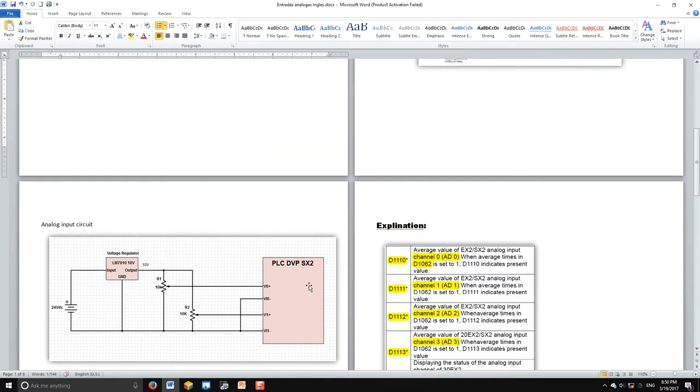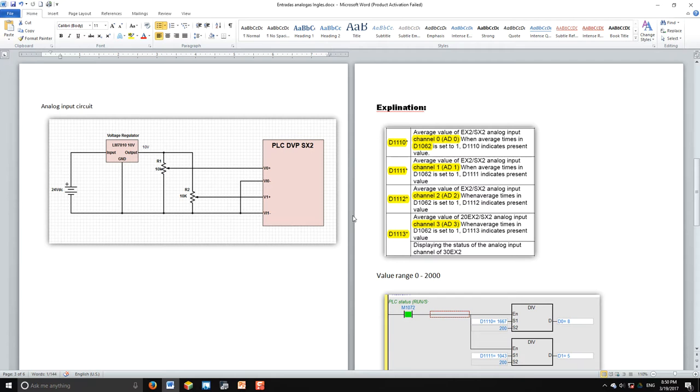Once your wiring is set up, it's time to read the voltage. To read the voltage, you'll use the D1110 address, which gives you the average value of the analog input on channel 0. D1111 gives you channel 1, which corresponds to AD1. These are the two channels we're going to use for this practice. The SX2 model has four analog to digital inputs total.